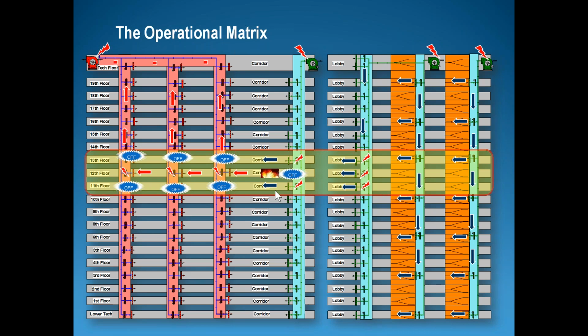And here we start the extraction. And you can adapt the variable speed drive to adapt the pressure. Because if you are feeding here, in this case, we are feeding at a point for each 3-4 floors with fresh air to pressurize the stair. But for low levels, for example, up to 4 floors, you can use single point pressurization. But how can we control the pressure here compared with this level here compared with this? So you have to have some variable speed drive or some air balance, to adapt the pressure to be homogeneous and uniform in all the vertical levels of the project.